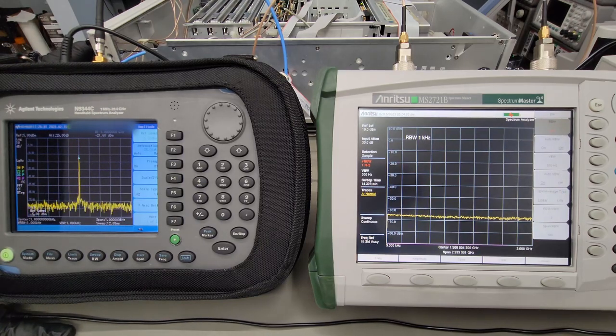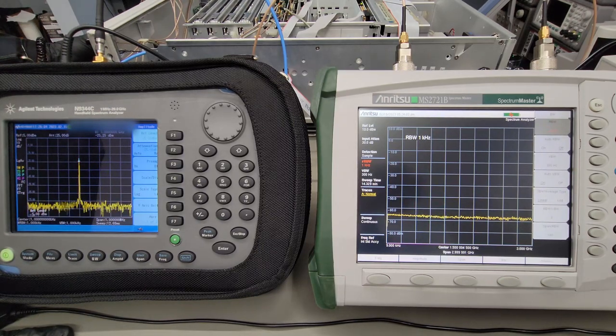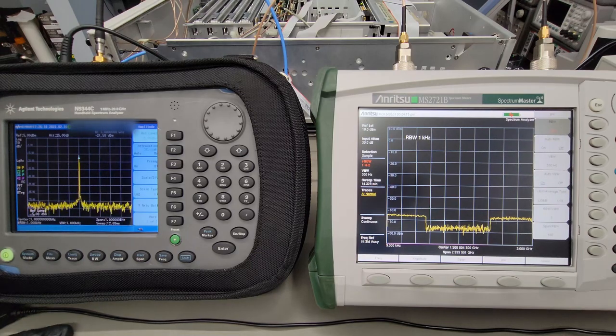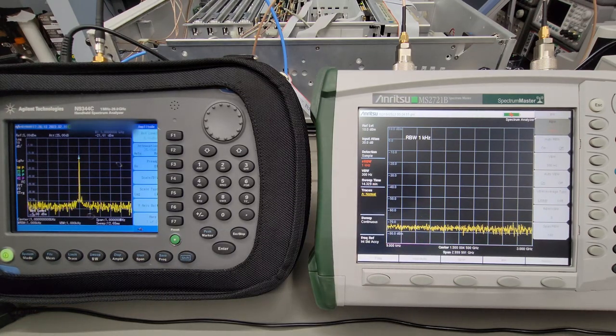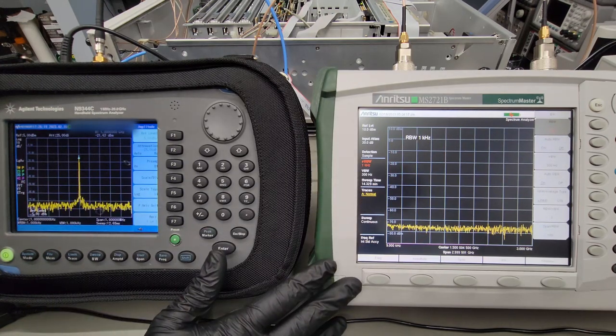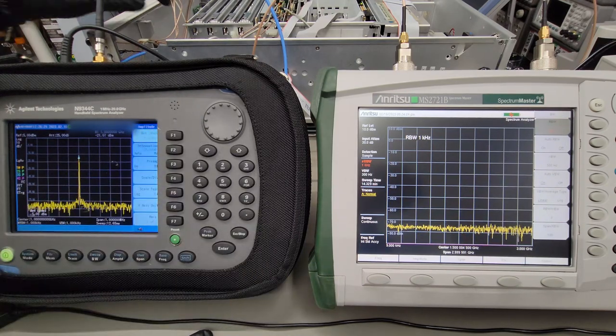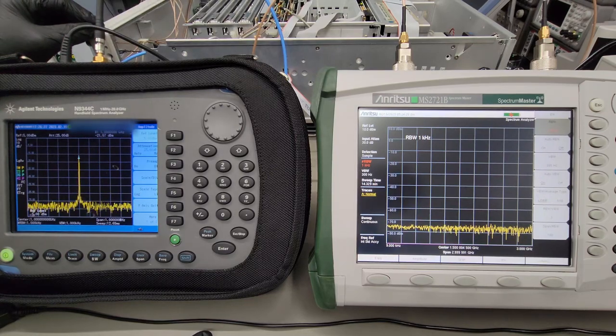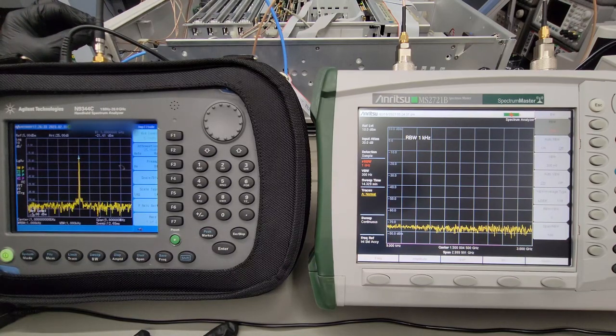And you can see now the instrument's set to minus 55 dBm. Minus 60, 65. So now we're getting pretty close to the noise floor here with our current bandwidth settings on the Anritsu. But you can see that the attenuator appears to be working throughout all its steps. So we definitely have to trace our way back, beginning at this detector here for the instrument. And we'll get into the architecture of the E8257C and try to figure out what exactly we should start measuring first. So here's the block diagram in the service manual for the analog PSG.